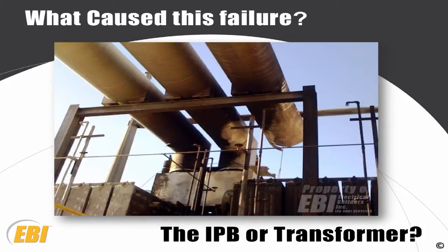As you can see here, this is a transformer where one of the doghouses is actually gone. Part of the IPB is actually gone. And with this, those pieces actually melted in 2/100ths of a second. When I was at this plant, you could actually see up against the side of a metal building about 200 feet away where the liquid aluminum splattered against the building.